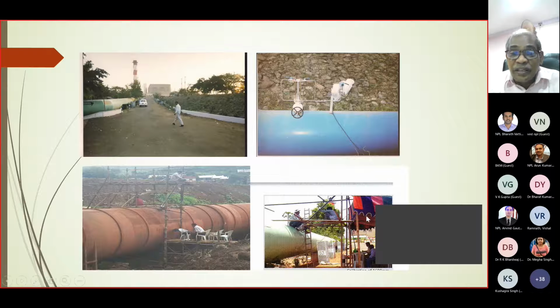See, if you look at these photographs, this is the water supply pipeline in Pune. The pipe is 3000 mm in diameter. We wanted to calibrate the electromagnetic flow meter fitted in this pipeline. So our people went there with a 1 meter length insertion flow meter. We inserted it this way, then on the opposite side, then vertically, at diametrically opposite places, to take the velocity survey. Then we have to average it.